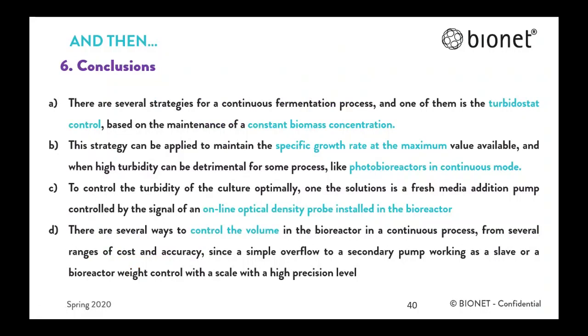Finally, some conclusions. There are several strategies for a continuous fermentation process, and one of them is the turbidostat, based on the maintenance of a constant biomass concentration. This strategy can be applied to maintain the specific growth rate at the maximum value available, and when high turbidity can be detrimental for some processes like photobioreactors in continuous mode. To control the turbidity optimally, one solution is a fresh media addition pump controlled by the signal of an online optical density probe installed in the bioreactor. There are several ways to control the volume in a continuous process across a range of cost and precision — from a simple overflow to a secondary pump working as a slave, or a bioreactor weight control with a scale offering high precision.